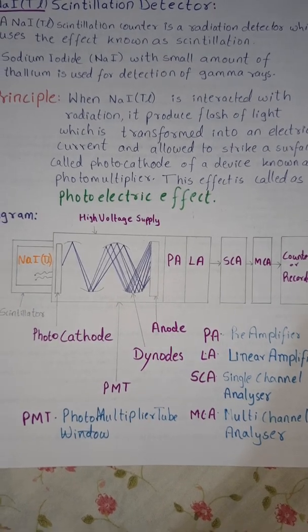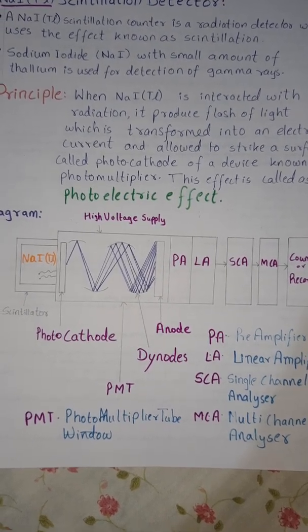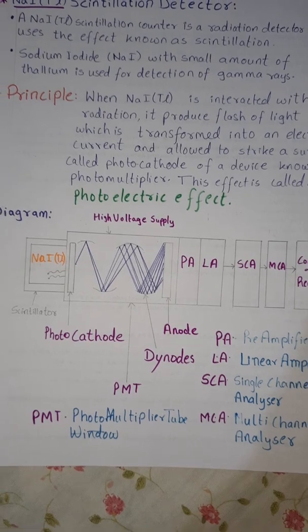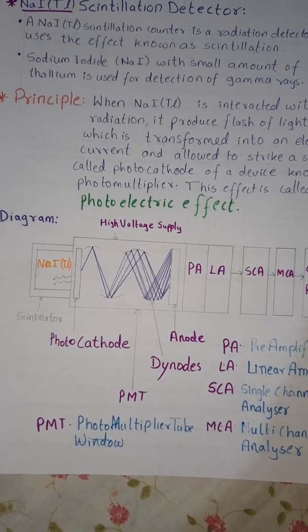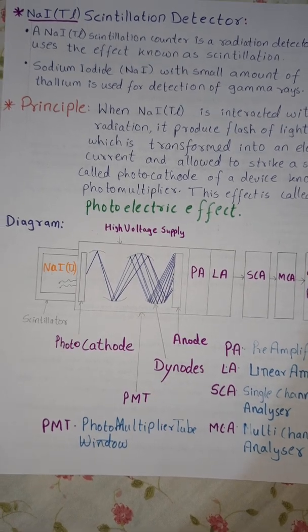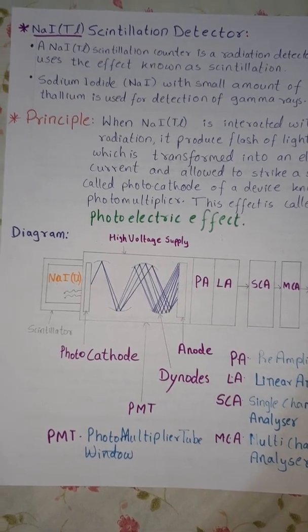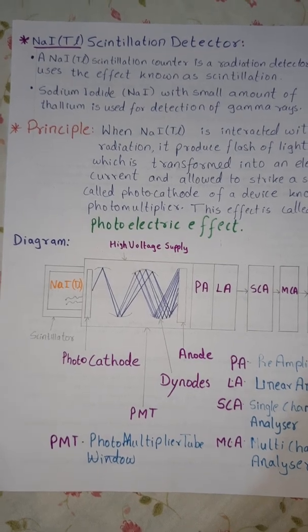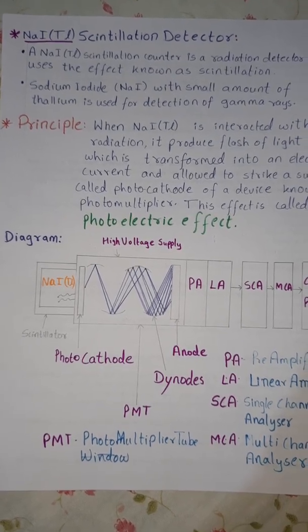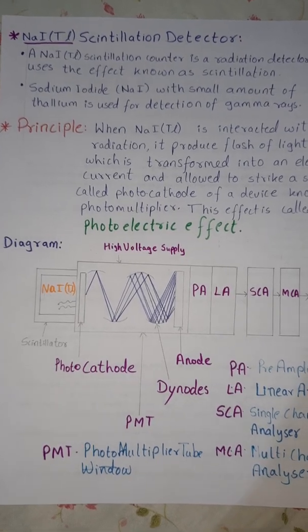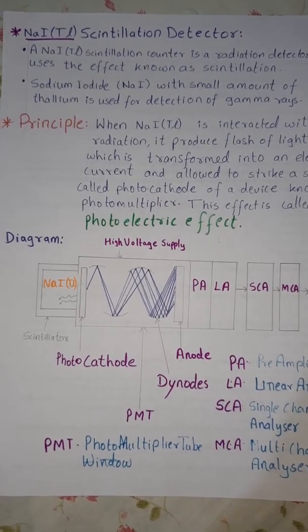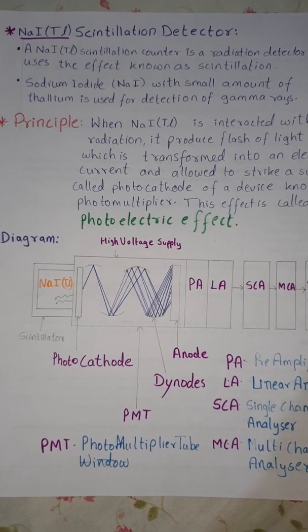There is a principle of photoelectric effect involved. When the electron absorbs energy, it goes to the higher energy level and then falls back to the lower energy level after some time. This travel time which the electron takes, there is emittance of light which is in the form of radiation. This is what is captured and this gets multiplied with the help of the dynode.